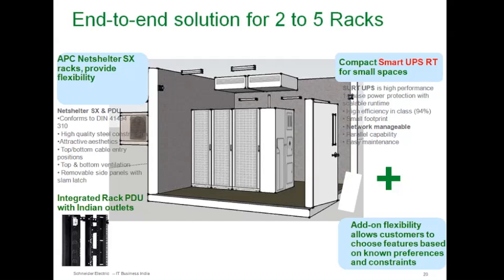Secondly, we've appropriately chosen technologies depending on budget. Comfort air conditioning is for cooling people, but for equipment cooling, precision cooling becomes very premium in this segment. So we created an offer based on high sensible cooling, which is much better than comfort cooling because it's designed for equipment cooling, though it does not provide precision cooling with respect to humidity control.